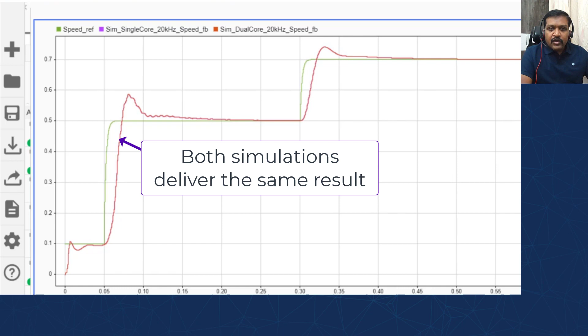On the top left, we can see from simulation results that we don't get an improvement by the dual core approach if the current loop runs by 50 microseconds and the PWM frequency is set to 20 kilohertz. But by using the dual core approach and raising the PWM frequency from 20 kilohertz to 40 kilohertz, which wasn't possible using a single core approach, if you maybe remember, we can see from simulation results that the rise time and speed will improve.